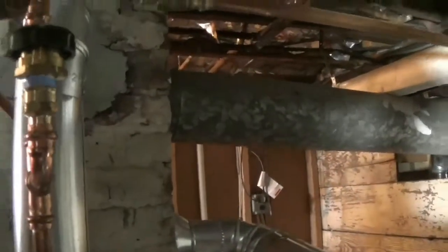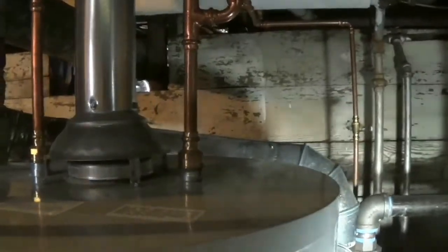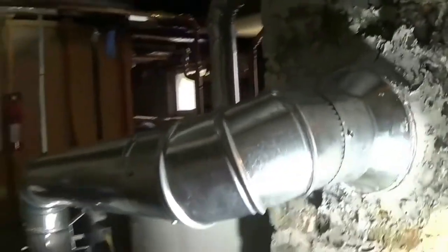You can see, in the case of the water heater, the draft opening, that draft hood, that little bell-shaped thing right down here at the base. This is where air mixes in. For the boiler, we'd have to get around the back there to see it, but there's a box off the back of it that is open on the bottom. And that is your draft hood for the boiler. So up inside there is where the combustion gases are coming out of the top of the combustion chamber, and you poke your probe way in there to get it where it's not diluted, so you get a raw sample of the carbon monoxide.